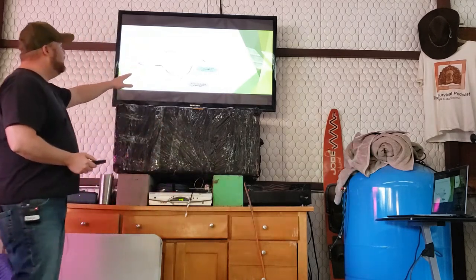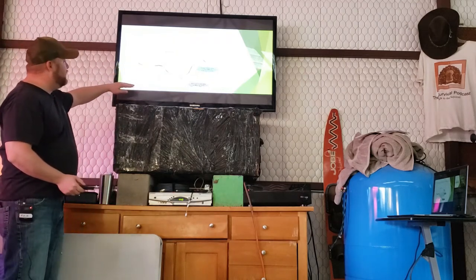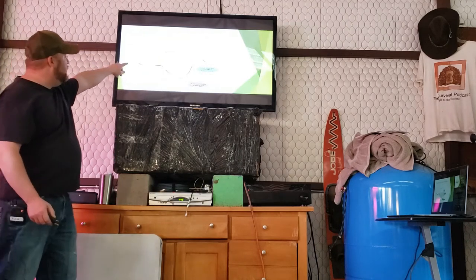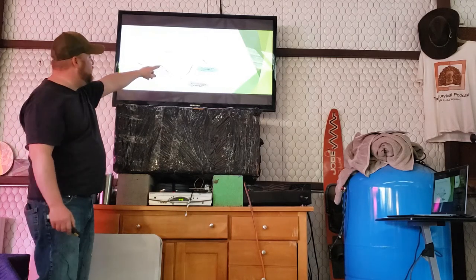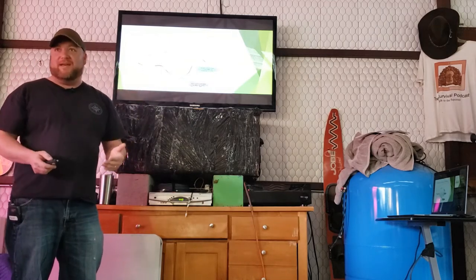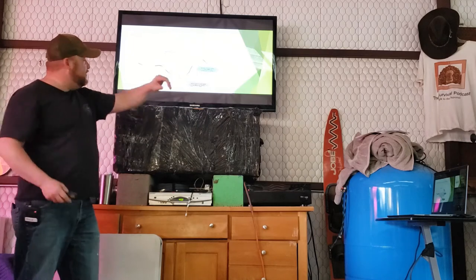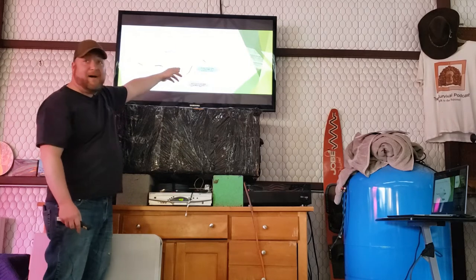So this is what's called the duck curve. This is the state of California, and this is the demand for electricity over 24 hours. It starts at midnight and runs to midnight. About 7 in the morning, people start having a higher demand for electricity. But that's also when the sun comes out, and because there are so many solar panels in California, the actual demand falls off a cliff. So this is what the utility companies are required to put on the grid. As you can see, it goes down, down, down till about 2 o'clock.